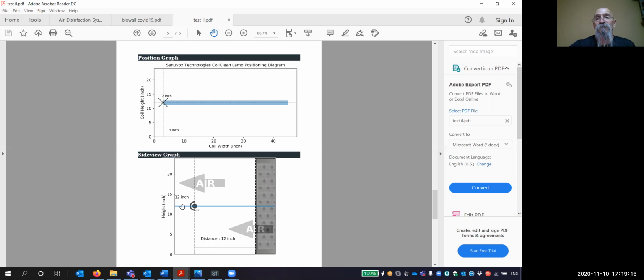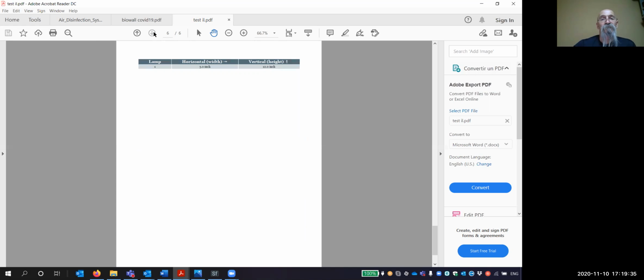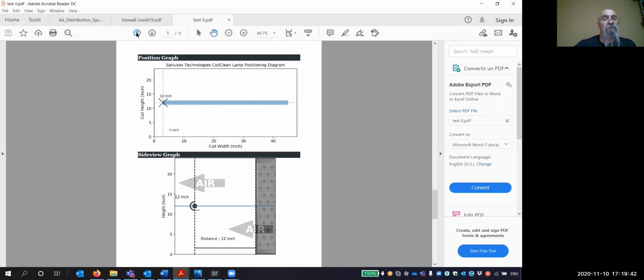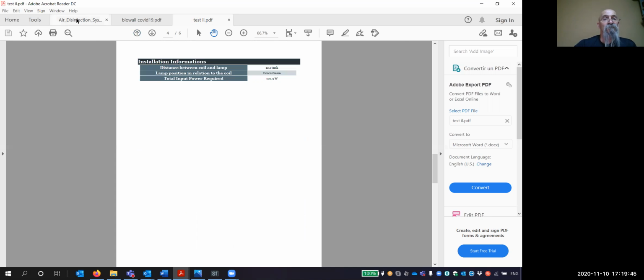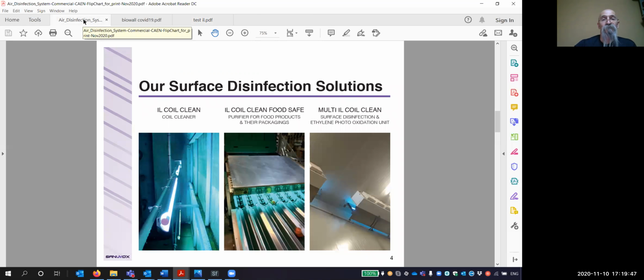So we've got a lot of air coming through, and if you have the lamp on the downstream side, that air will go against that lamp, and fouling will happen. The preferred location obviously is the upstream, where the air is coming in from behind the lamp going through the coil. And then this one just sizes out exactly what position, mathematically, measurement wise. So that's just an example of the coil cleaning and such.